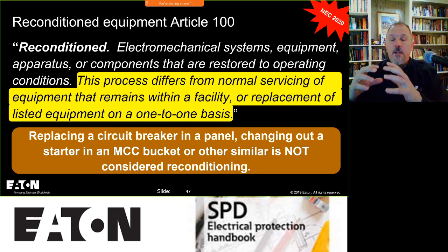Now, it's important that you separate this definition from any other definitions you may have in mind. You may have another document, from some other standard or organization, or part of your own procedures, that may say what you're doing in your facility is reconditioning. You may say, well, performing regular maintenance on my equipment is considered reconditioning because it says so in this other document. None of that really matters when it comes to the National Electrical Code, because the NEC is going to look at its own definition of what reconditioned is. And that's the critical part of this whole thing.